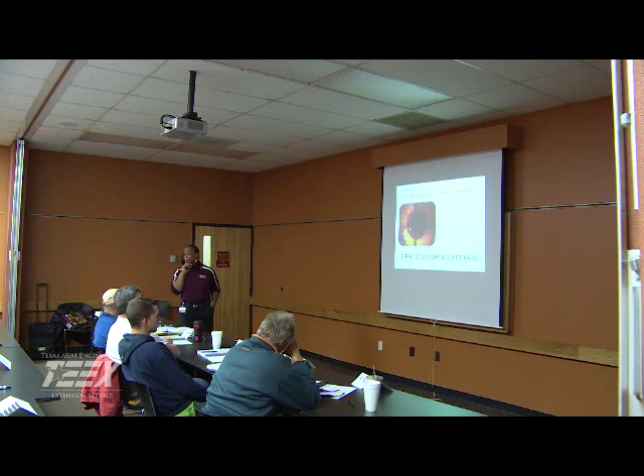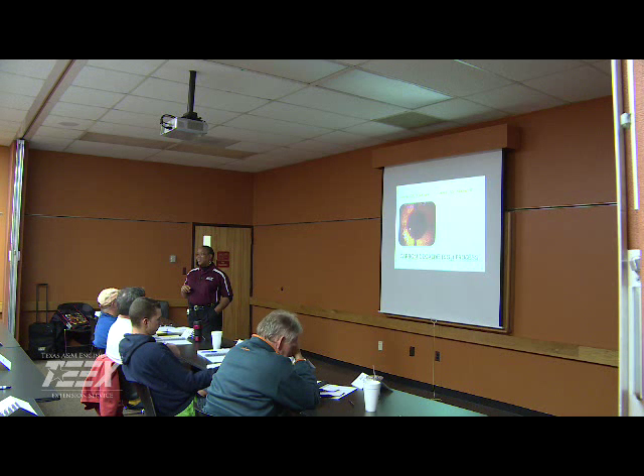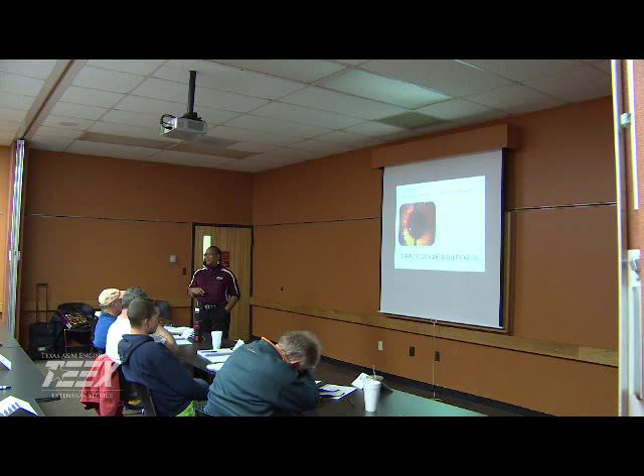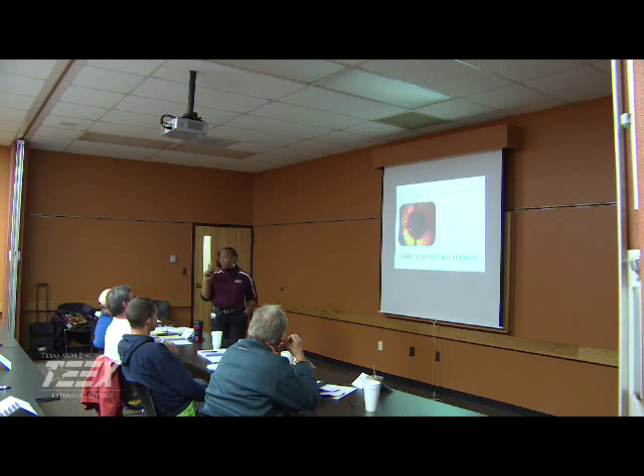This fellow that does my well once a year, he's got a TV camera. He goes down before and after, so you're not getting gypped, you know. Excellent. These people used to run around and paint your pipe. They had a bucket of paint and a paintbrush, and they'd go. They'd tell you they went in there and saw so many pits they could fix for you and all this. That doesn't work anymore. Absolutely. The inspector goes in there and makes pictures, fixes you a book when he gets done, and then when he gets through painting and cleaning, he gives you another book. Excellent.